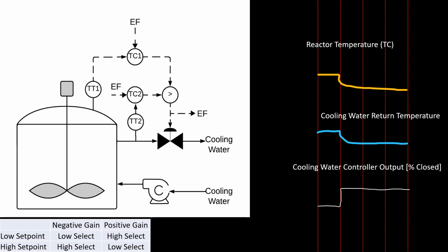This video will begin our series on override control. In general, you map one controlled variable with one manipulated variable. However, with many systems, there are more controlled variables than manipulated variables. Therefore, when a system arrives at an abnormal condition and a controlled variable goes outside its desired limits, then a manipulated variable needs to be used to drive this controlled variable back into its normal operating range.